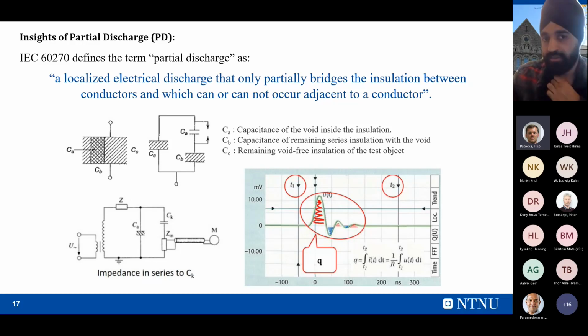Now this is the way to measure the charge present inside that void. This is a direct method, but we cannot measure directly. So for this, we need to connect something external. This is the test object, the object which I am going to test, and it has some void inside. To measure the amount of charge inside that void, we need to keep a coupling capacitor externally, the one which I have shown in this picture.